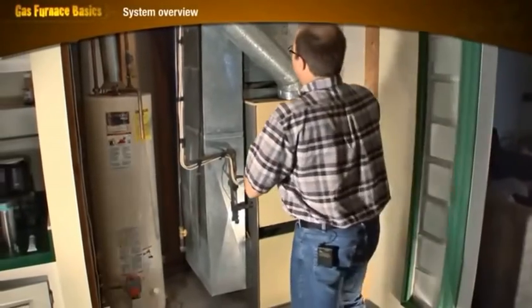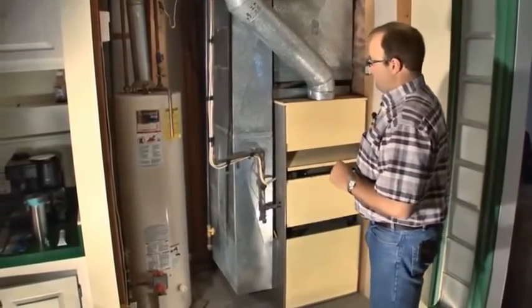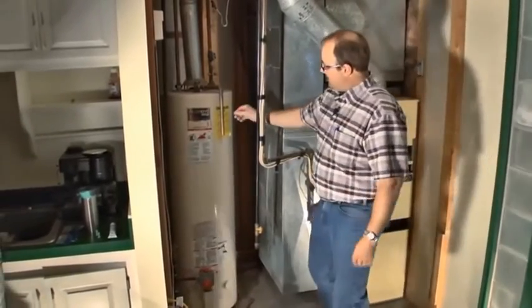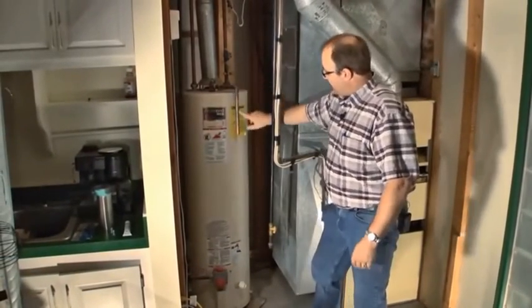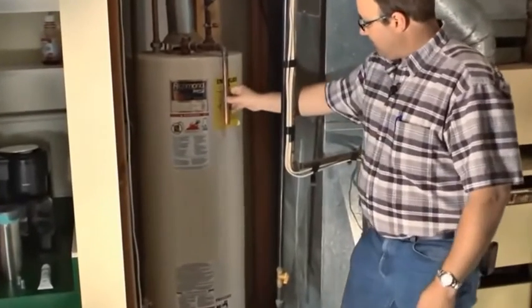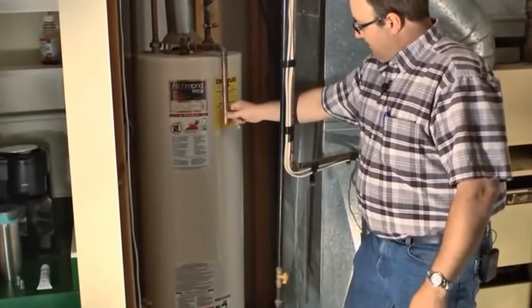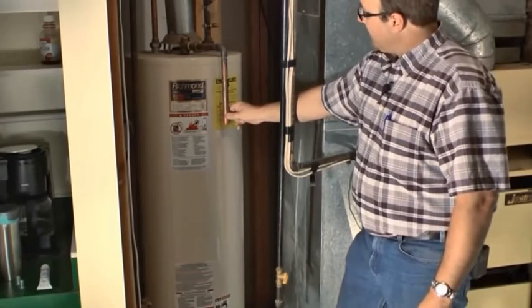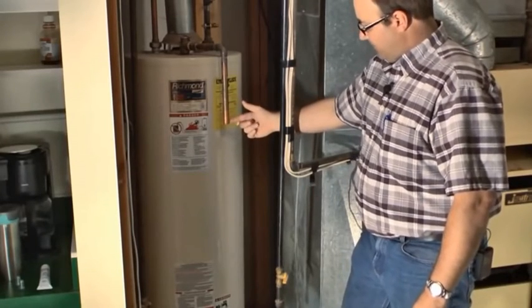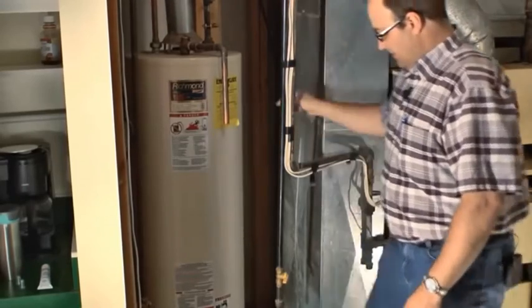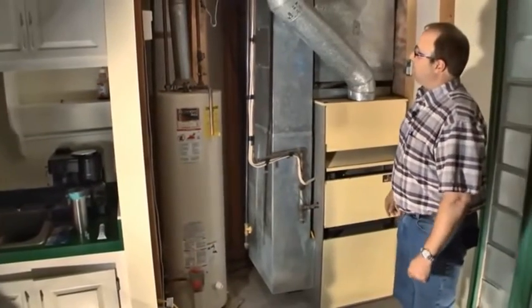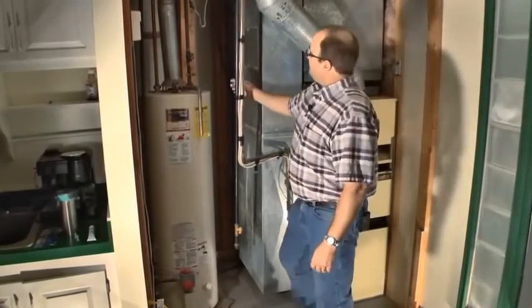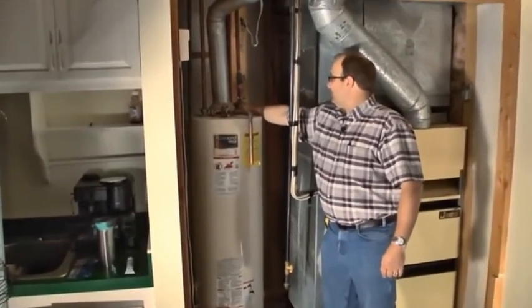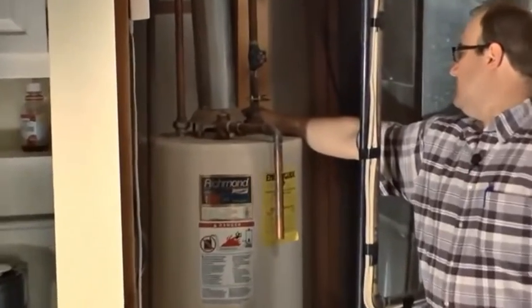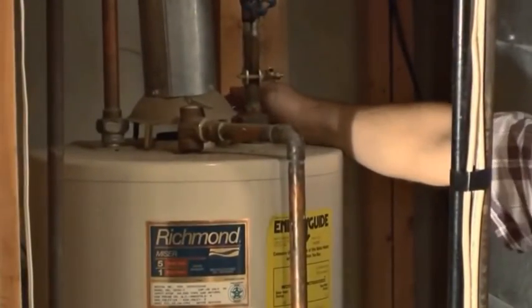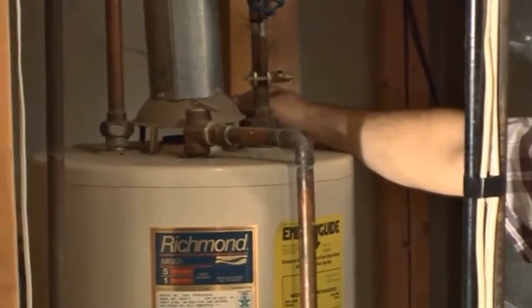Okay, so a couple more things we'll take a look at on this unit are these two units. Looks to me like this is the relief valve for the water heater. I know we're talking about furnaces here, but this is supposed to be within around 6 inches off the floor. And so we would actually prescribe an addition of some pipe to this to get it to the floor. That's a code requirement. Another thing I noticed is the draft hood on this is part of it's out of its place. It's kind of at an angle. We'll probably try to fix that as well.